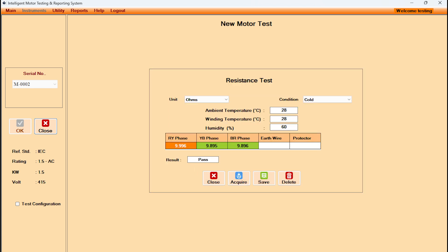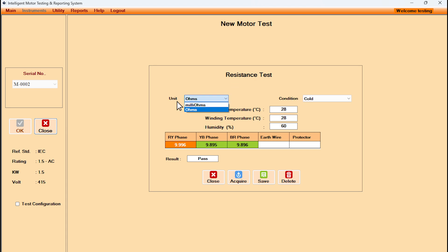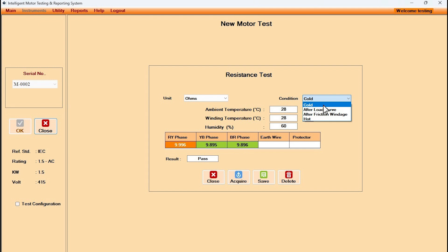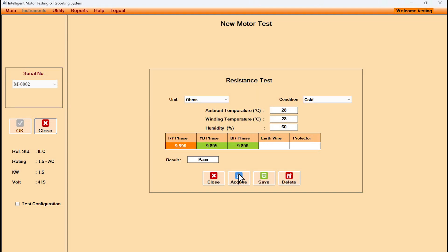While conducting winding resistance test, unit of measurement is displayed. Winding resistance measurements may be done up to four times. By clicking on the acquire button, temperatures, humidity, and all resistance values get populated in the table. Software allows to set pass and fail criteria based on minimum and maximum values for each of the parameters.